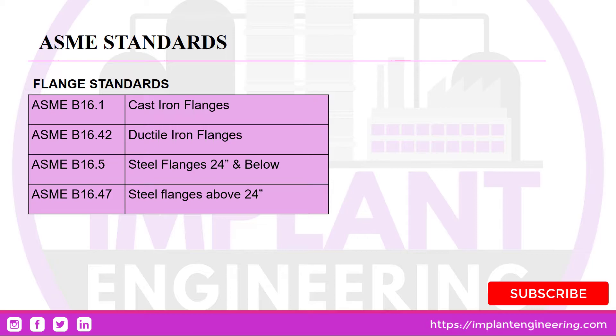Here are a few ASME standards. The first are flange standards. ASME B16.1 indicates cast iron flanges. ASME B16.42 is used for the designing and construction of ductile iron flanges. ASME B16.5 covers steel flanges up to 24 inches diameter. ASME B16.47 is used for the designing and construction of steel flanges above 24 inches diameter.